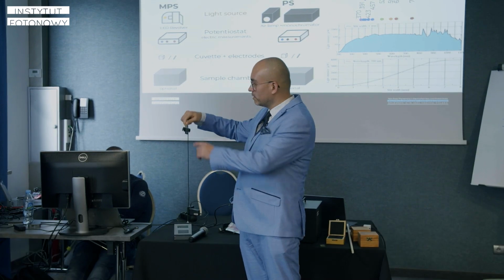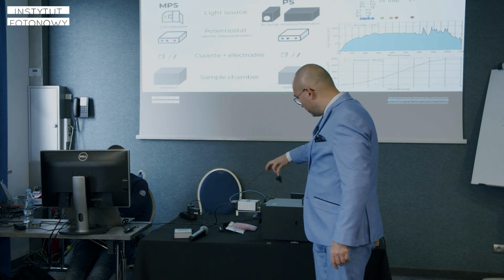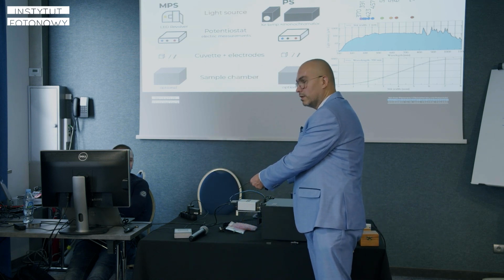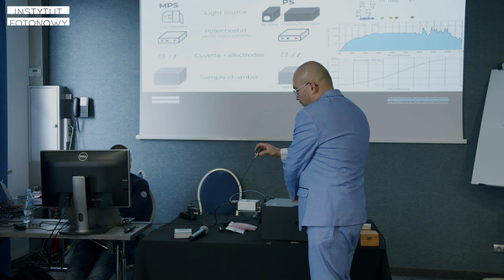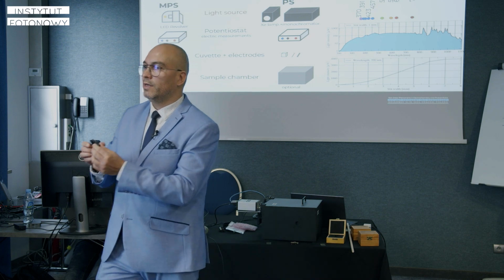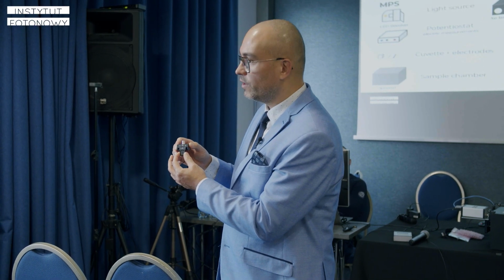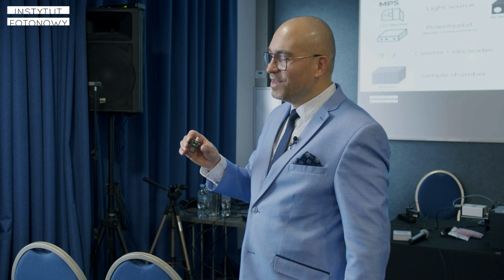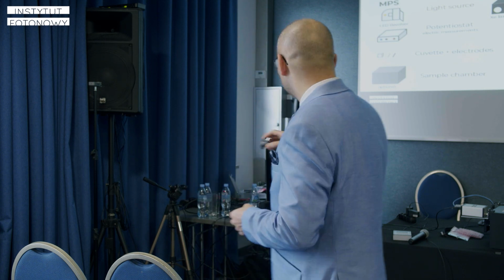This is the calibrator head. We have another BNC feed through, so we can place this calibration head exactly in the spot where the sample is, and we can read the value of the light which is reaching the sample. Then, if we repeat the experiment, we know the value of light, and all other parameters are the same. We don't change anything, and we place the sample in the same spot and connect the sample.